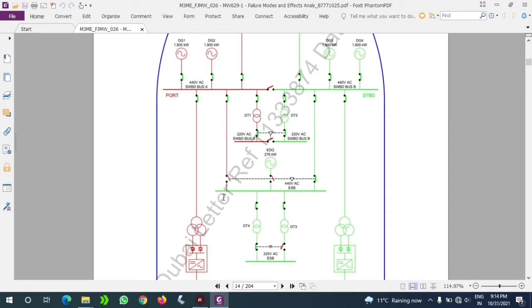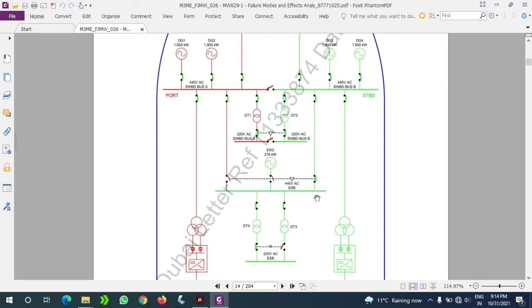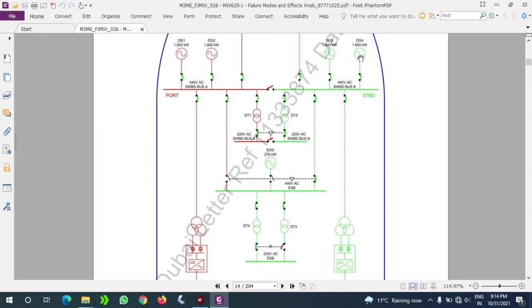What is basically an ESB? It's an emergency switchboard. Emergency switchboard consumers will be connected - essential consumers only, basically like starting air compressor, emergency lightings. You should note the point that this is a 440 volt emergency switchboard bus bar, so our emergency lightings are not going to work from 440V. We need 230V for that, which I will come to later.